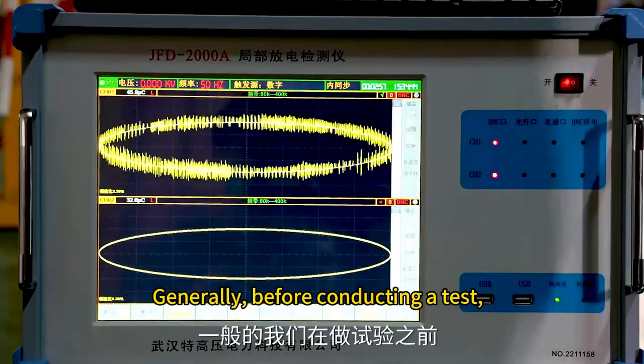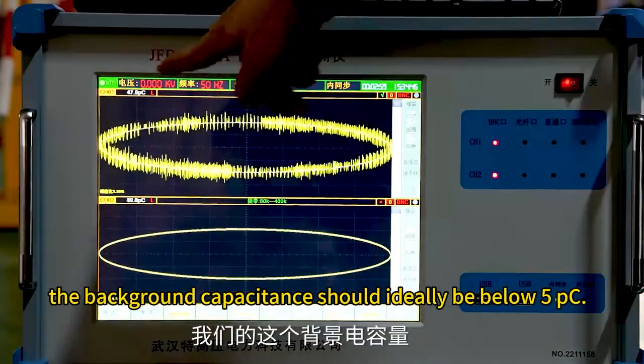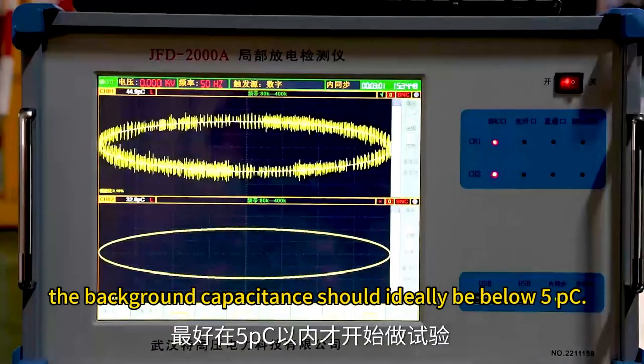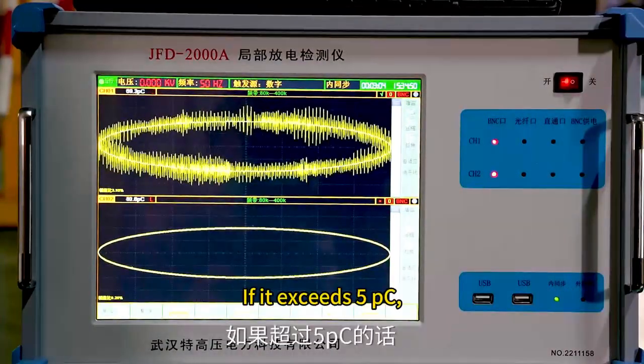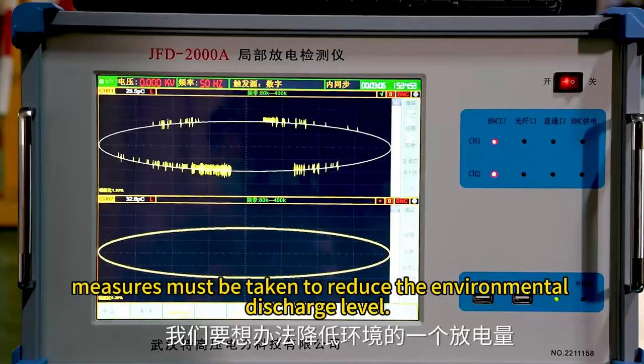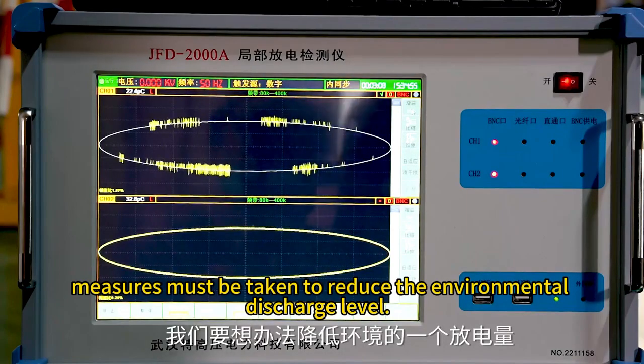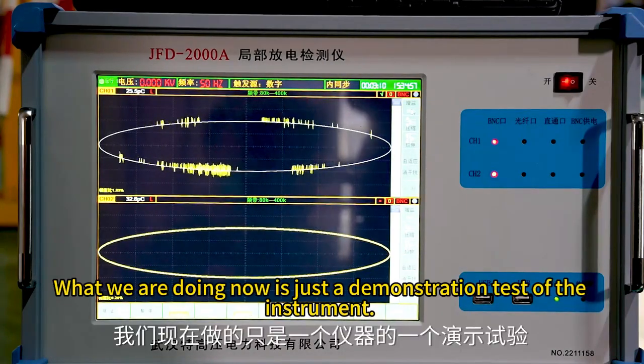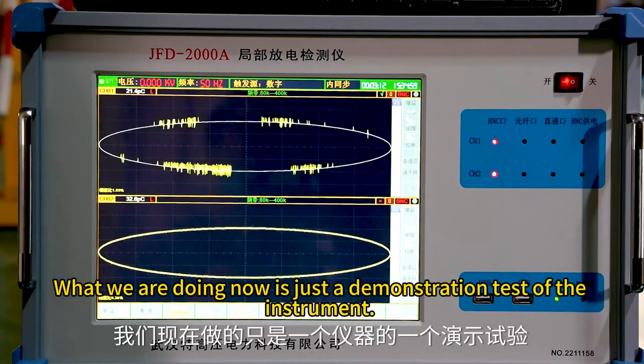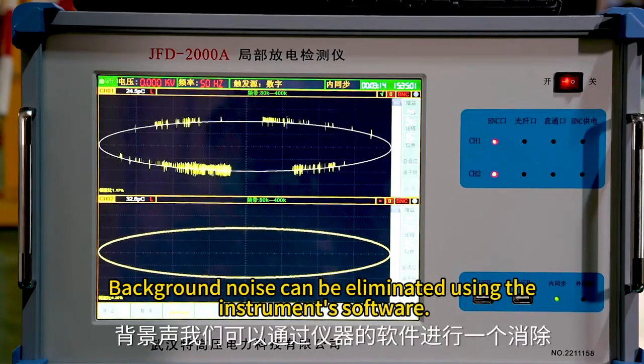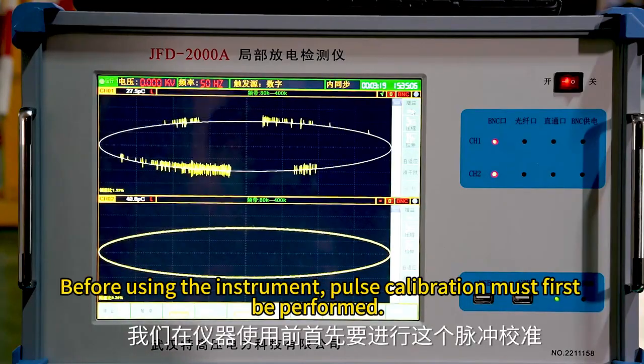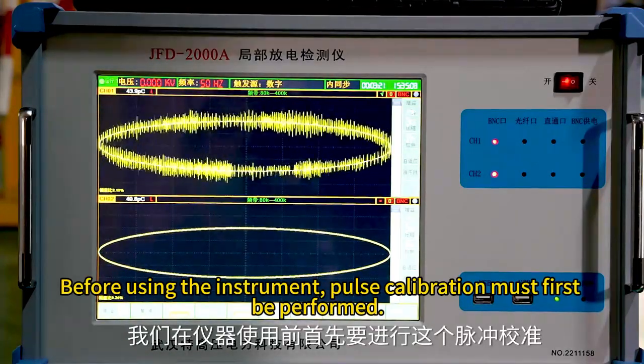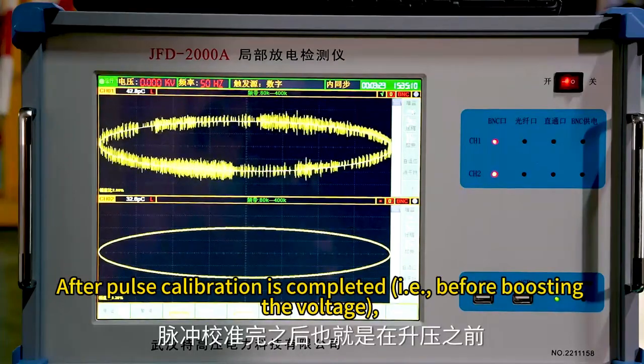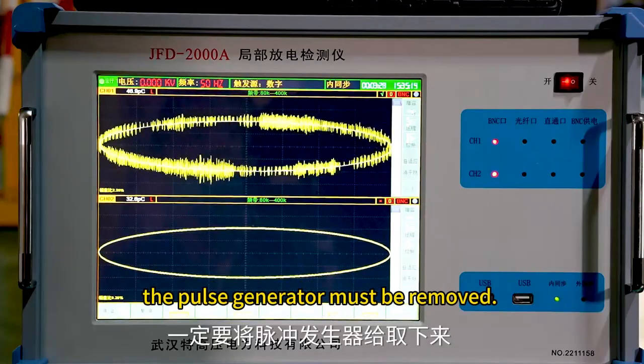Generally, before conducting a test, the background level should ideally be below 5 pC. If it exceeds 5 pC, measures must be taken to reduce the environmental discharge level. What we are doing now is just a demonstration test of the instrument. Background noise can be eliminated using the instrument's software. Before using the instrument, pulse calibration must first be performed. After pulse calibration is completed, before boosting the voltage, the pulse generator must be removed.